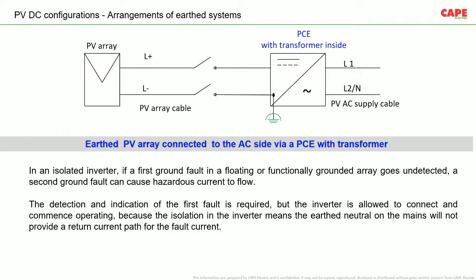Now, in this particular case, this is a PCE with a transformer inside. That means the inverter has an isolation transformer inside, so the AC side and DC side are electrically isolated. Under this condition, you see here the negative in the picture. The negative is functionally earthed. I am sure you are aware of this functional earthing, symbol 5018. Functional earthing is made for certain applications. It is not for safety. It is not a fault return path. It has to do something for the functioning of the whole system. That is how it is.